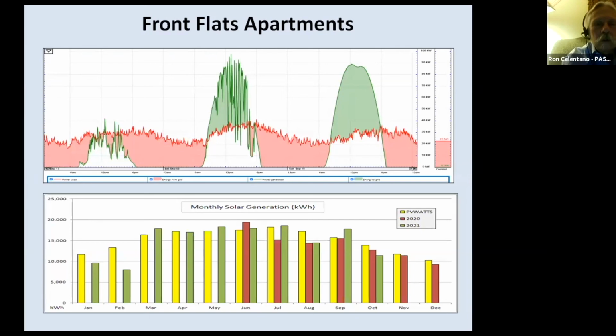I'm close to the last slide here. This is the monitoring system, again e-gauge, showing 3 days of generation with a relatively flat load shape. On good days we're doing almost 100 kW, I've seen over 100 kW generated. This is the gross usage, not net. This demonstrates the monthly solar generation compared to PV Watts, what was originally simulated.